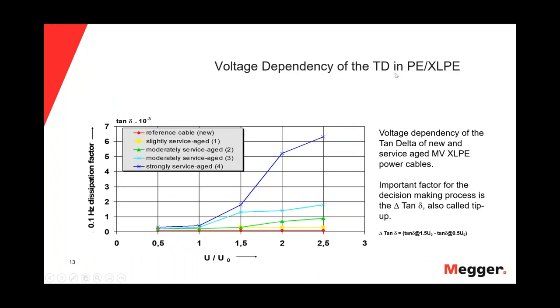This slide shows voltage dependency of the Tan Delta. The red reference cable is new, yellow is slightly service-aged, green is moderately service-aged two, then moderately service-aged three, and strongly service-aged. The important factor for the decision-making process is the Tan Delta, also called tip-up. Looking at 1.5 times U0 for the aged cable, you can see a dramatic jump up from new to moderately aged to service-aged. These are the values that come into play.